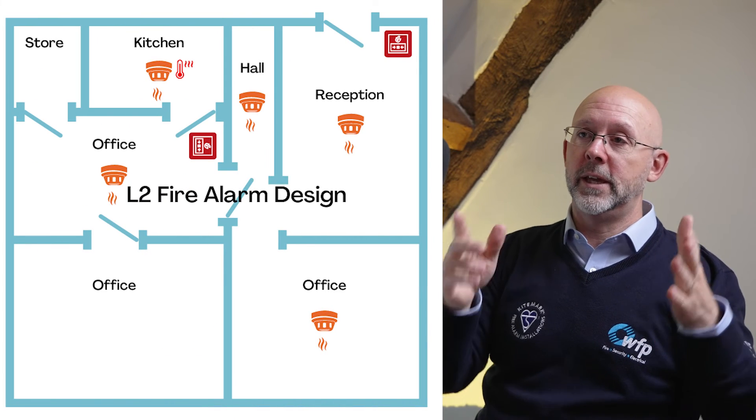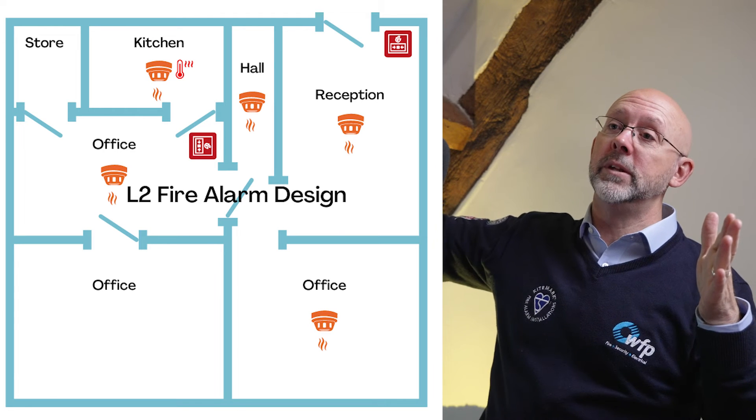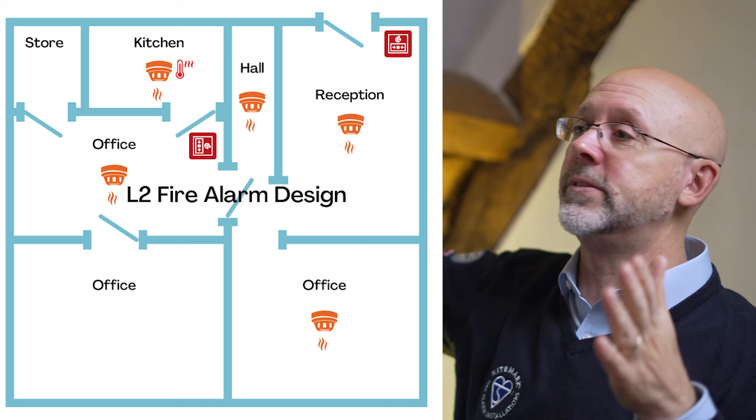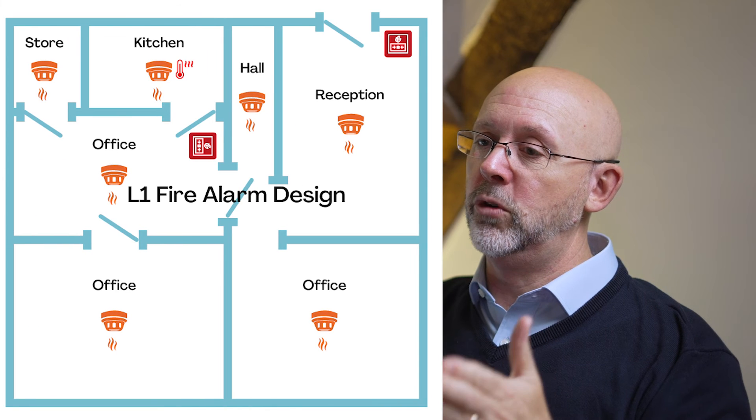With an L3 system, even if a large room would normally require five detectors, you'd only put one, because you're only worried about smoke leaving that room and affecting the escape route. L2 is exactly the same as L3, except the fire risk assessor has identified specific high-risk areas within rooms — such as server cupboards or plant rooms — that warrant additional detectors. One or two of these additions make the difference between L3 and L2, so L2 is essentially a bespoke version of L3.